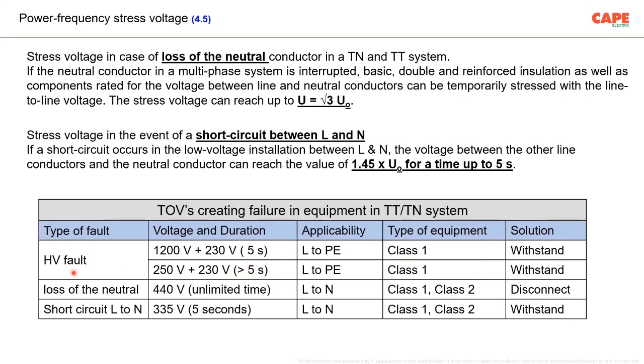So basically, your equipment is supposed to withstand the two conditions mentioned here, both the voltages 1200 or 250 plus 230 volt. Of course, the electrical designer or the energy supply company shall ensure that the voltage is limited to a level lesser than this. Don't cross 1200 volt. It should be lesser than 1200 volt. Then only the system will work. They have to make that particular arrangement.